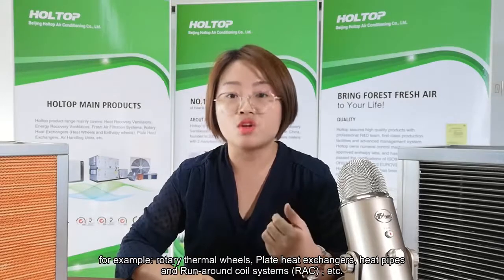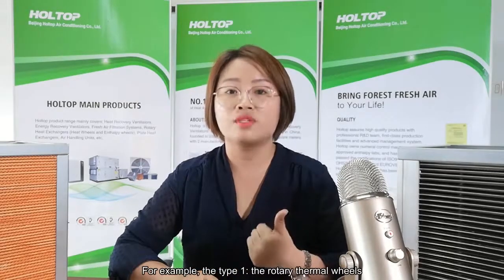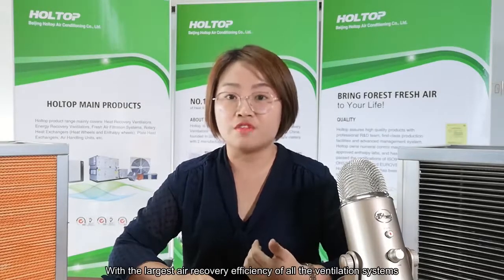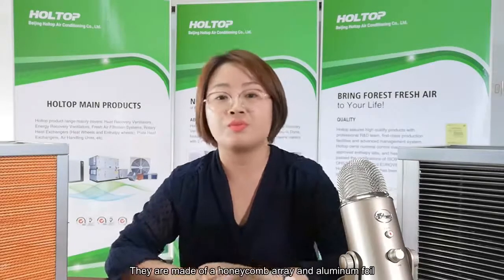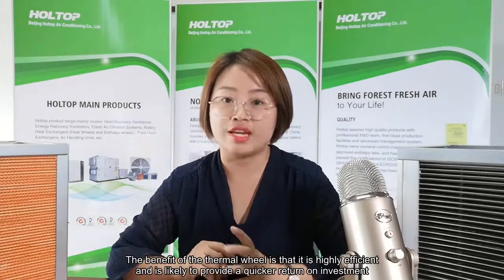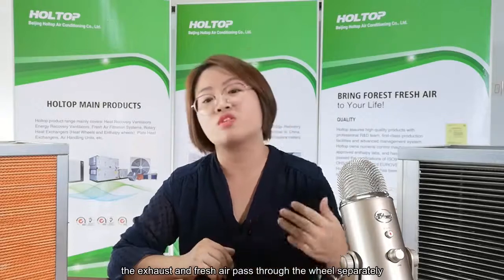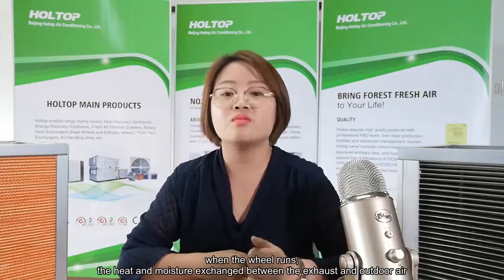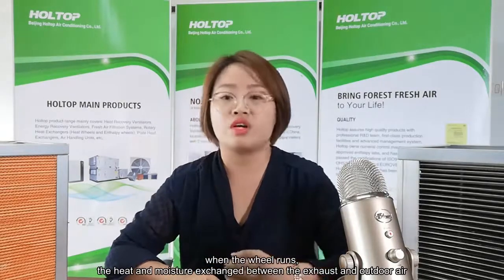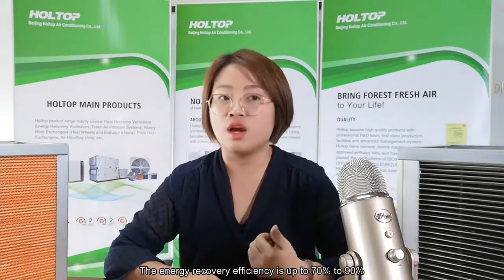Well, energy recovery ventilation systems can come in a variety of forms, but all involve some form of heat exchanger. For example, the rotary thermal wheels, plate heat exchangers, heat pipes, and run-around coil systems. We also call it RAC. So let me explain it one by one. Type 1, the rotary thermal wheels. With the largest air recovery efficiency of the ventilation systems, thermal wheels also tend to be bigger in size. They are made of a honeycomb array and aluminum foil. The benefit of the thermal wheel is that it is highly efficient and is likely to provide a quicker return on investment. For example, in the Holtop thermal wheel, the exhaust and fresh air pass through the wheel separately. When the wheel runs, heat and moisture are exchanged between the exhaust and outdoor air. The energy recovery efficiency is up to 70 to 90%.